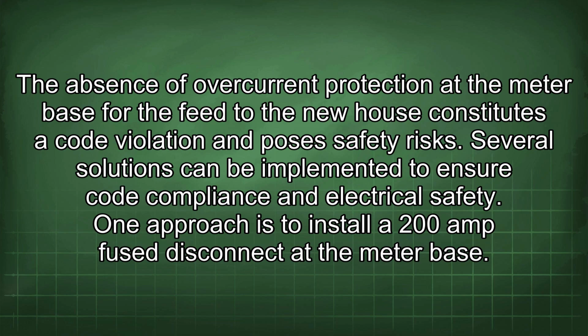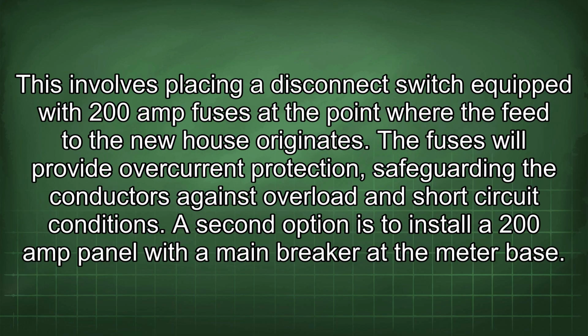One approach is to install a 200 amp fuse disconnect at the meter base. This involves placing a disconnect switch equipped with 200 amp fuses at the point where the feed to the new house originates. The fuses will provide overcurrent protection, safeguarding the conductors against overload and short circuit conditions.